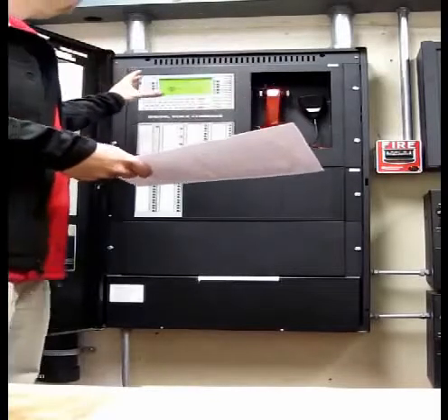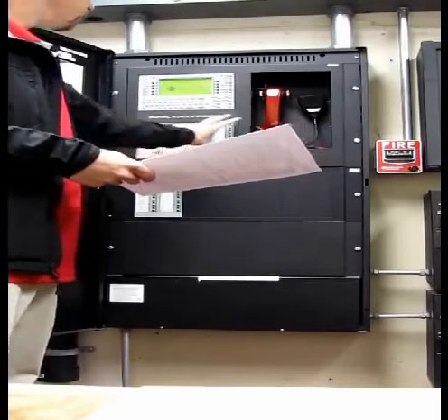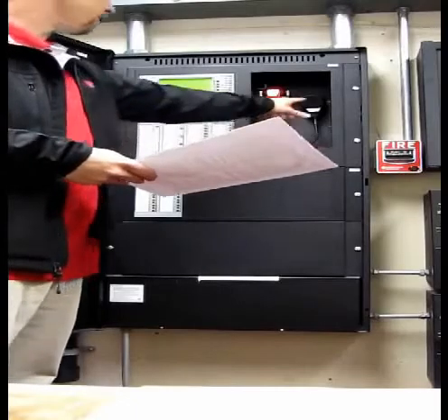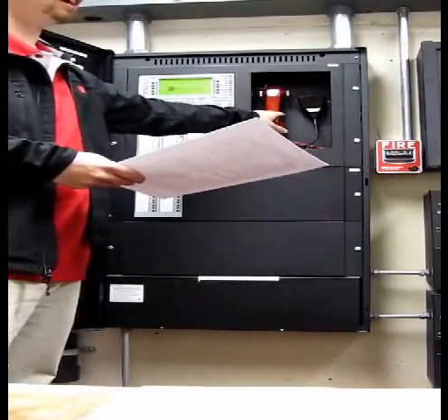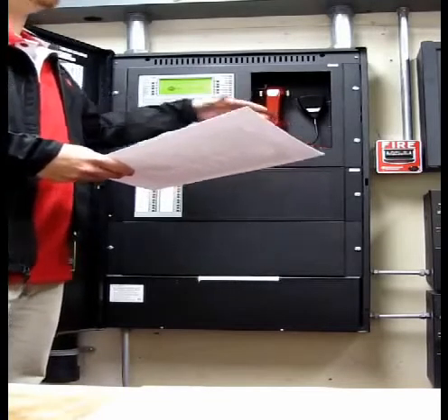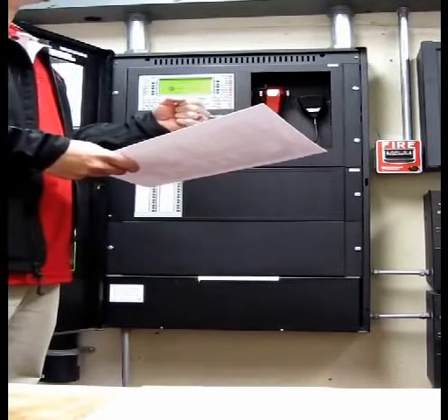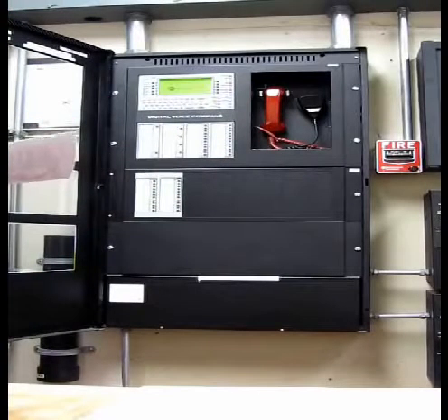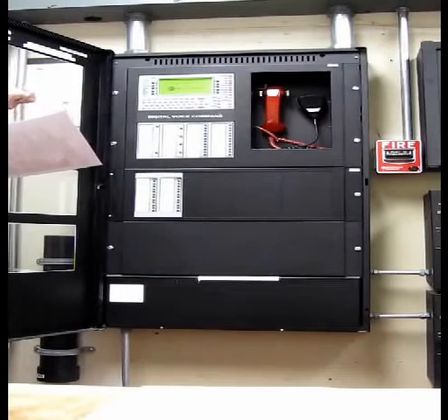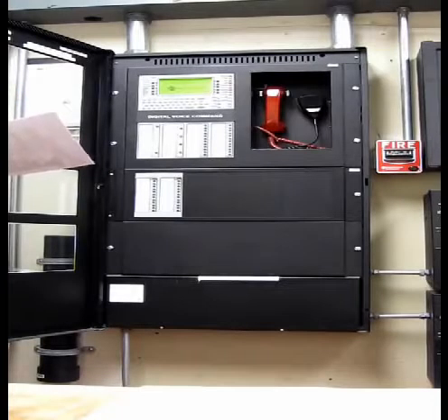Okay, so this is the main panel, the 3030, and you have your DVC, the Digital Voice Command Center, with a microphone and a handset for the fire department. You guys won't really be messing with the handset. What this is for is if the fire department comes in response to an alarm and their radios don't have communication in the building, they can come over here and grab a handset from here, and then they have the plug-in devices in the stairwells and by the elevators that they can plug into and talk back and forth.